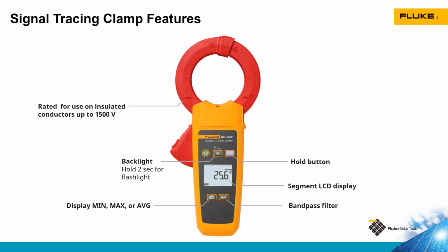Also, that backlight button, if you hold that for 2 seconds, right at the top of the yellow section of the tool, there's an LED that turns on that becomes a little flashlight there. The current measuring clamp also has a band pass filter that will filter out the high frequency component of the signal, which allows you to more easily trace the signal in systems that have high capacitance especially.